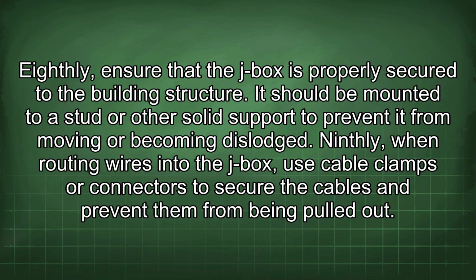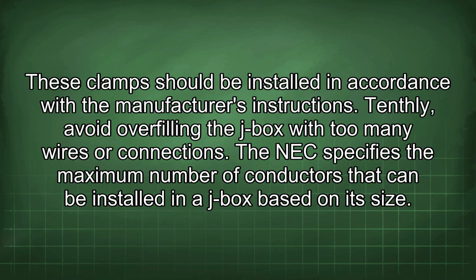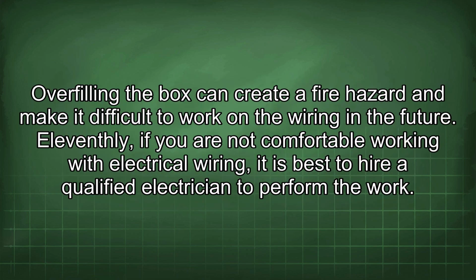Ninthly, when routing wires into the J-box, use cable clamps or connectors to secure the cables and prevent them from being pulled out. These clamps should be installed in accordance with the manufacturer's instructions. Tenthly, avoid overfilling the J-box with too many wires or connections. The NEC specifies the maximum number of conductors that can be installed in a J-box based on its size. Overfilling the box can create a fire hazard and make it difficult to work on the wiring in the future.